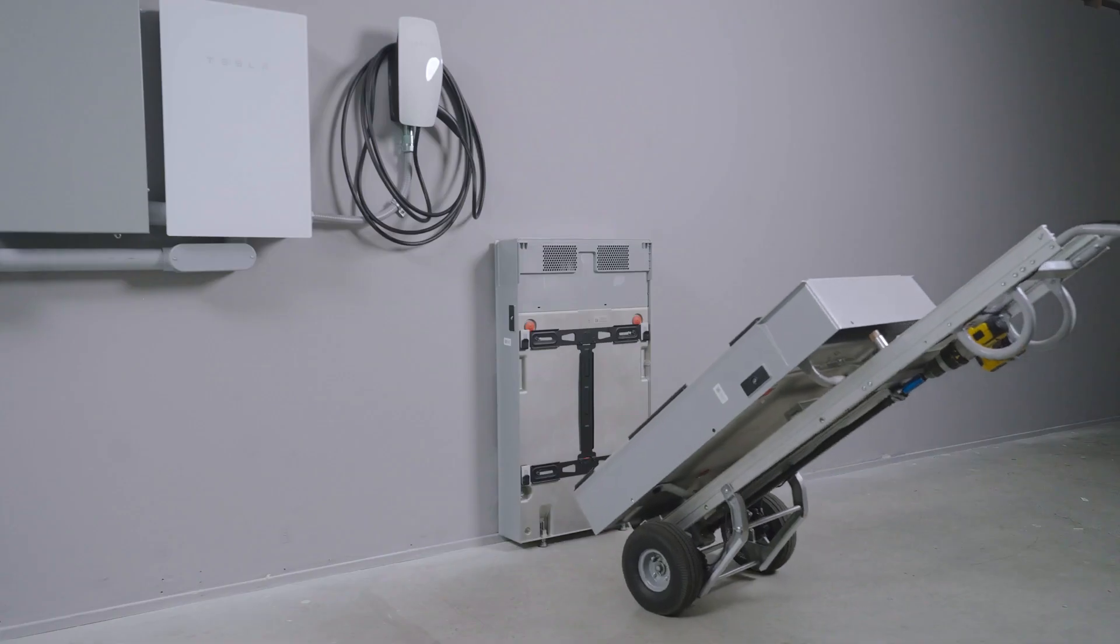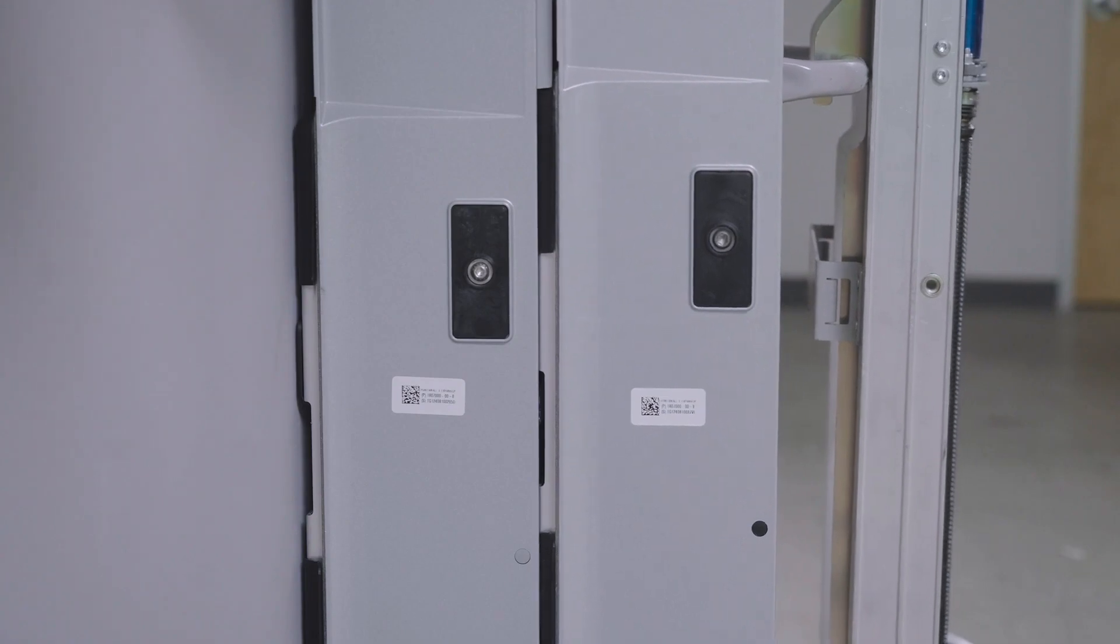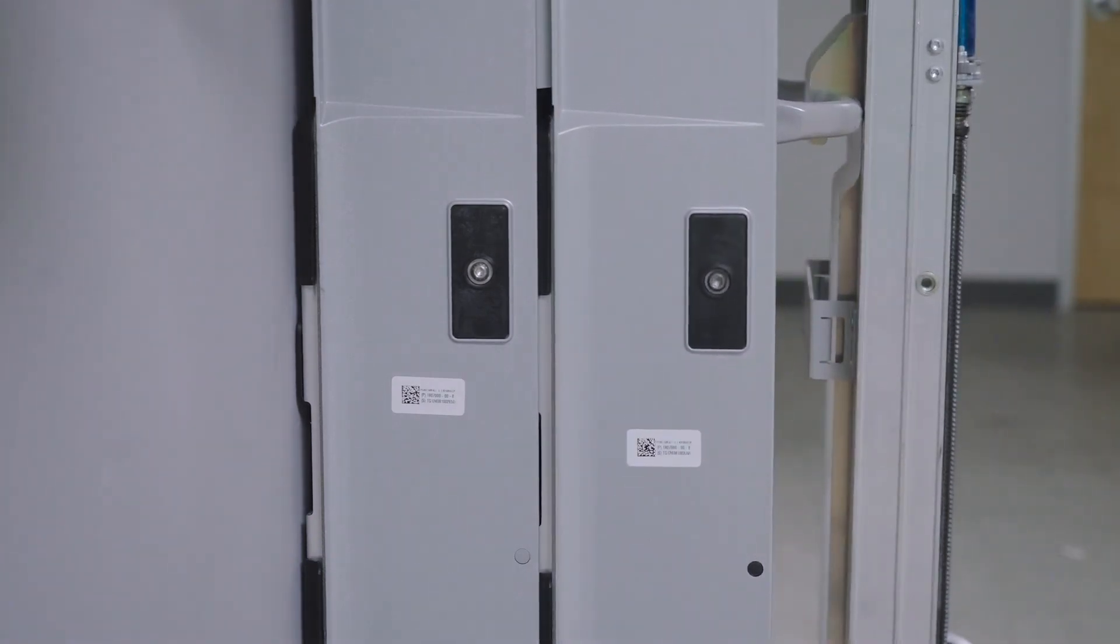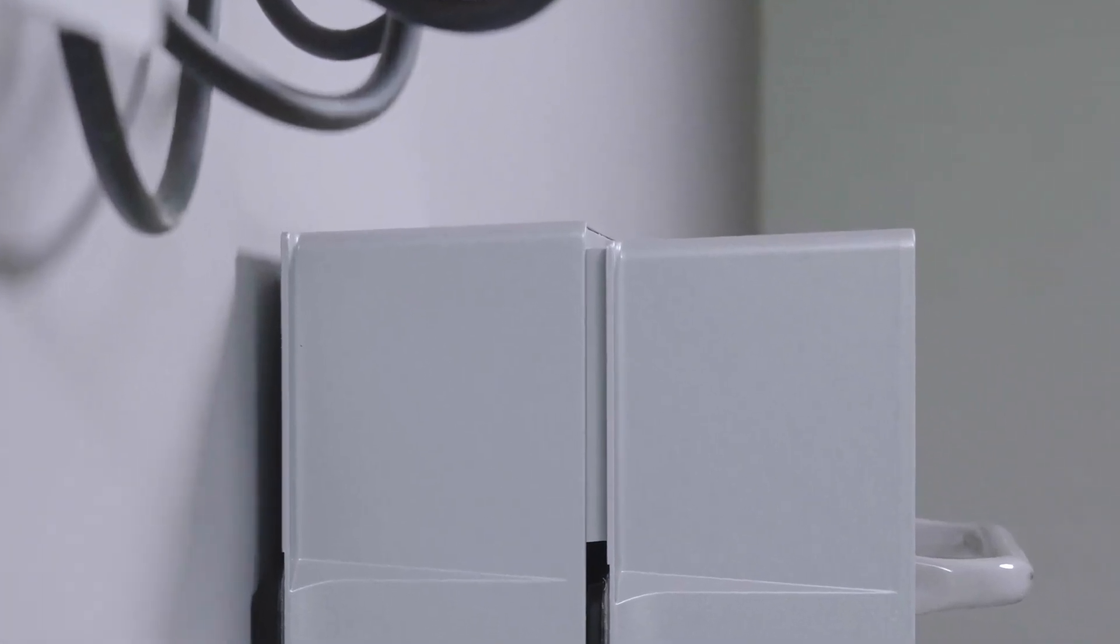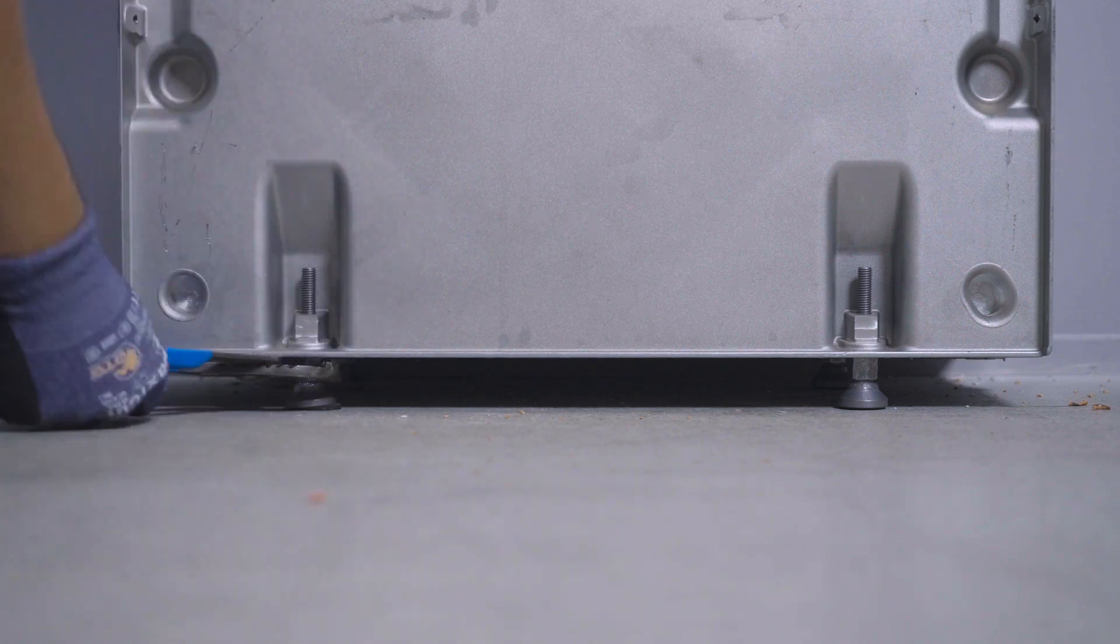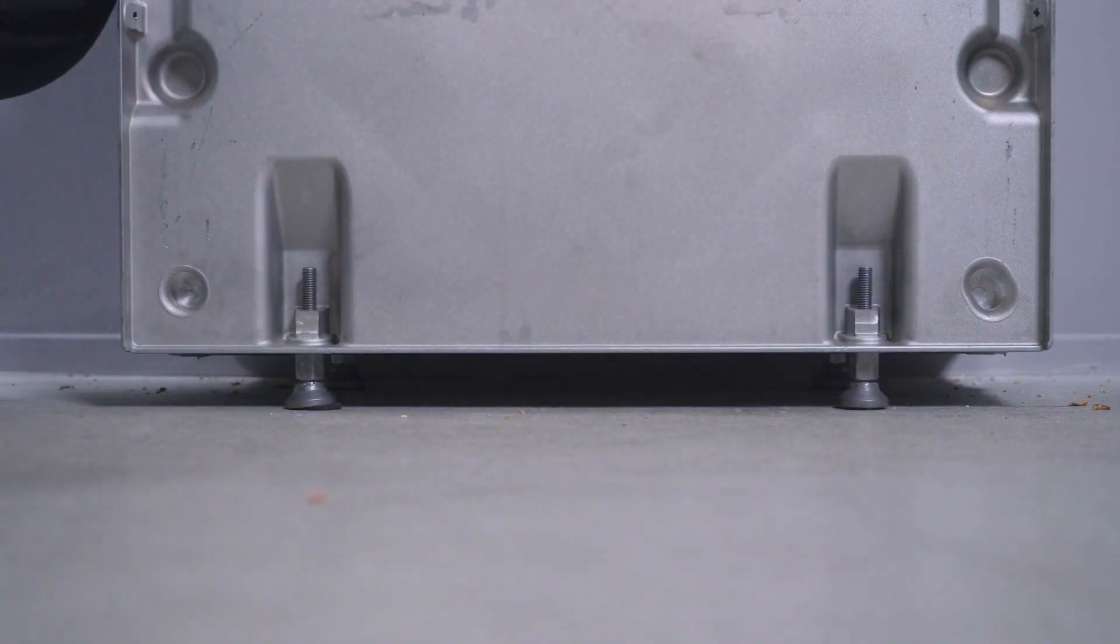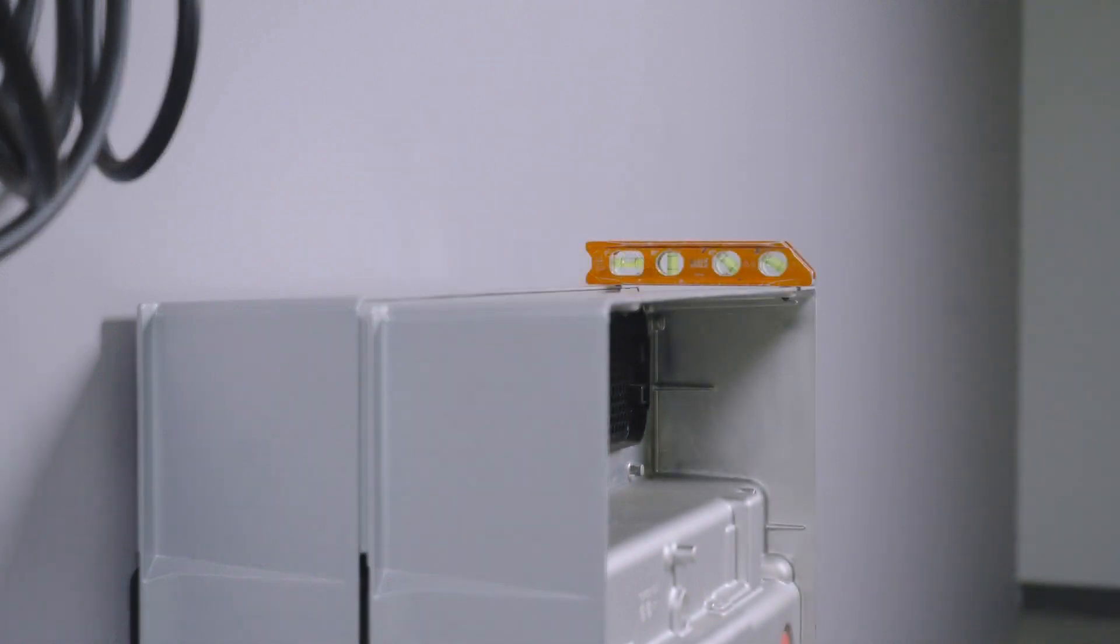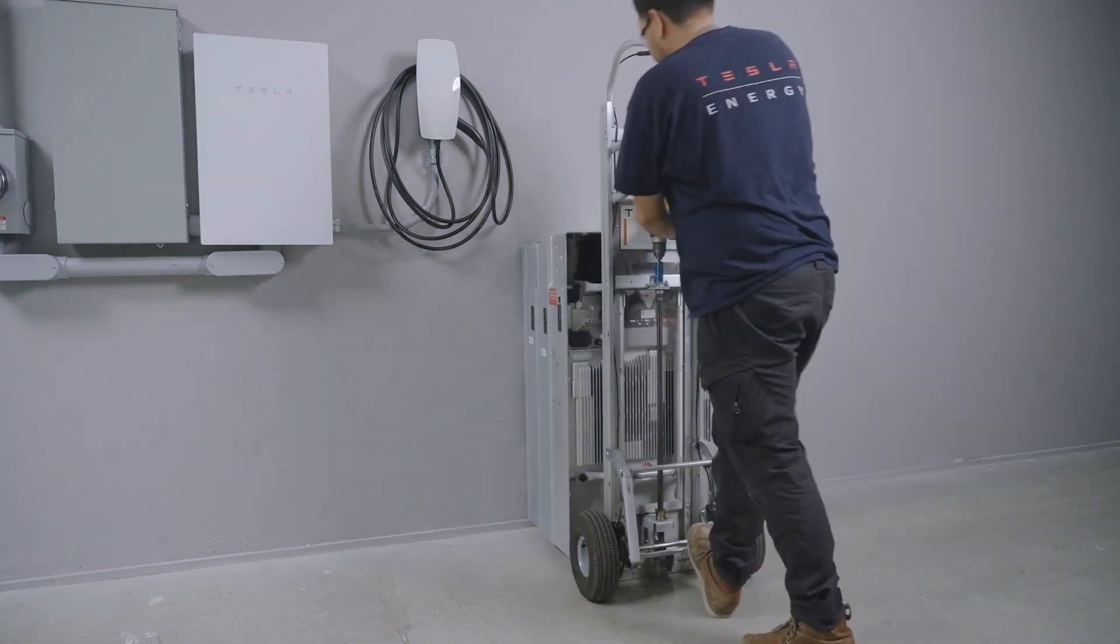Gently lower the next unit in the stack onto this bracket, either Powerwall 3 or another Powerwall expansion unit. The front unit will sit slightly lower than the unit it is mounted to. Adjust the leveling feet to align the mounting level of each unit. To ensure that the whole stack is level, place a torpedo level on the front edges of both units at the far left and far right ends of the stack. Repeat these steps for a stack of up to four units.